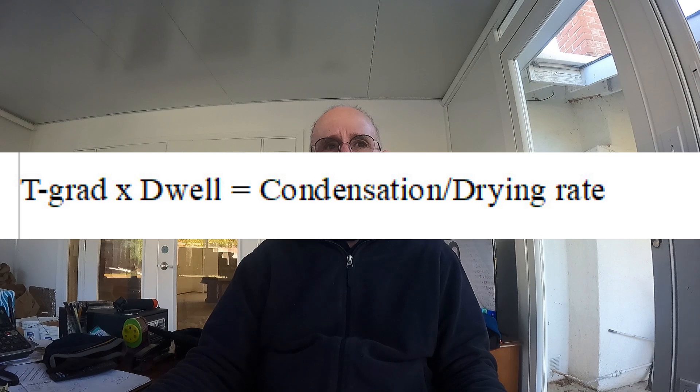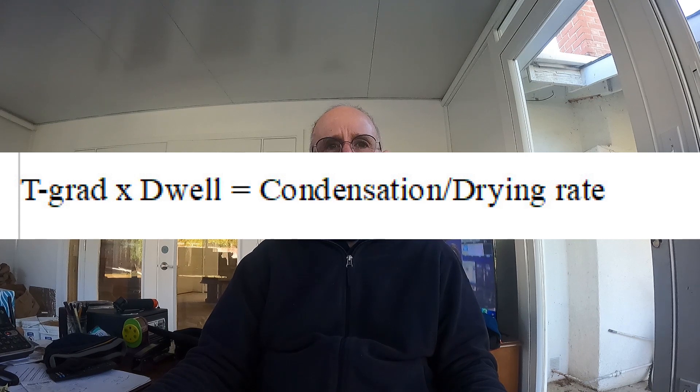We want to optimize both of these factors. The following is a simple logic equation for this relationship: the temperature gradient times the dwell results in a condensation drying rate. The PDP temp is very different from the atmospheric dew point temp. The higher the air pressure, the higher the PDP temp, which results in a faster condensation and drying rate.